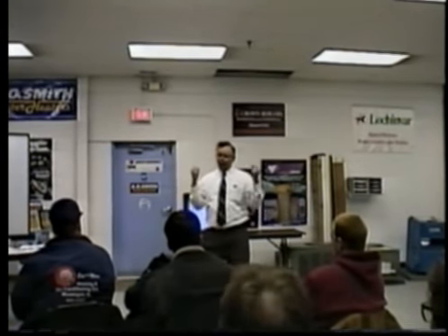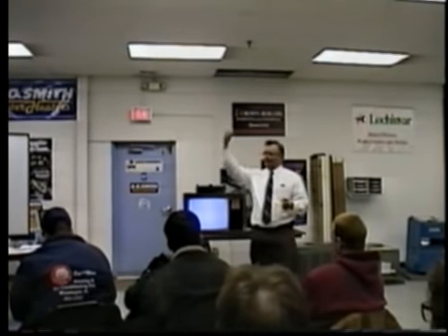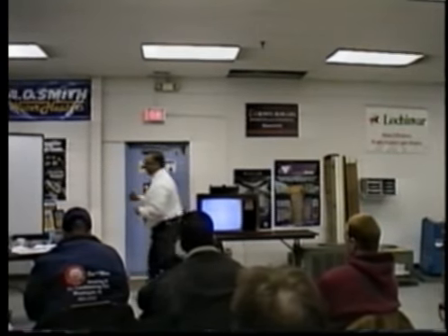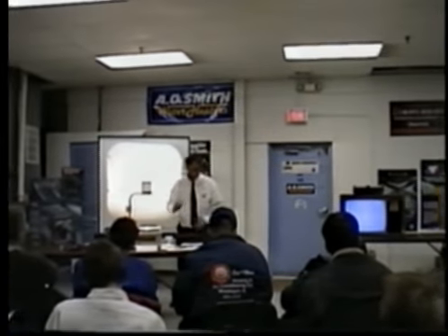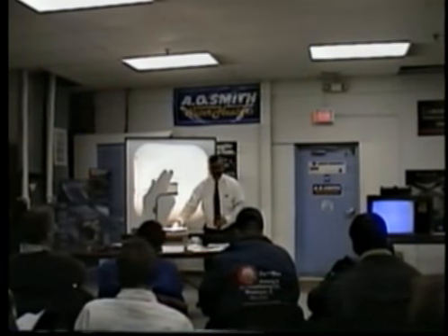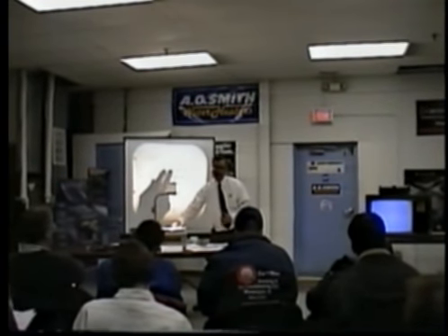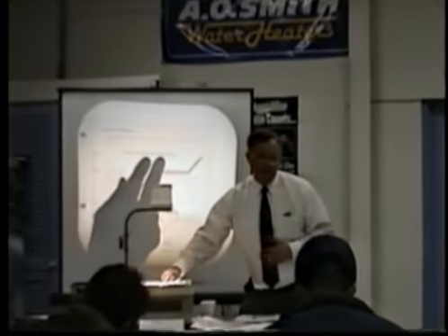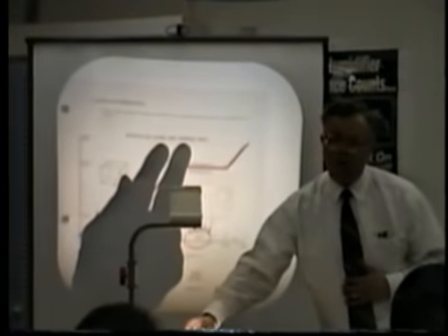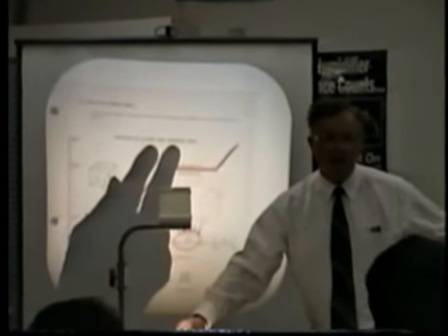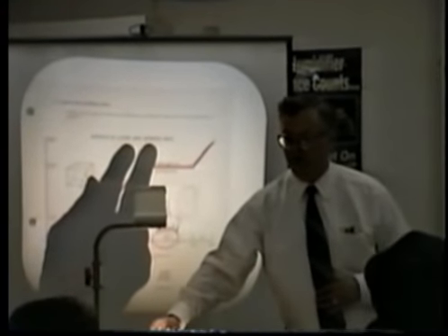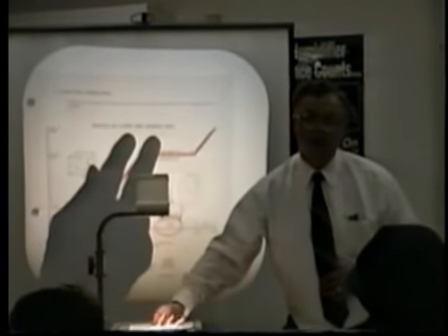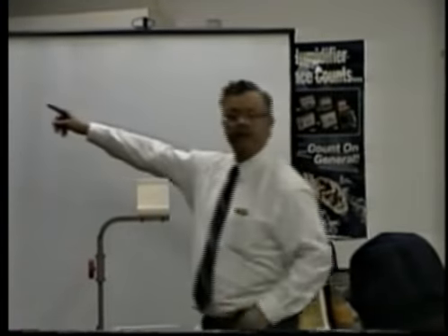So you have to size an air conditioner not only to handle the sensible heat, but the humidity, because that is the total heat load. The total heat load for air conditioning is latent and sensible heat. The air conditioner must handle both, and that's all figured into the charts. Now you understand why an air conditioner might not work on a hot day, and it's pouring water down like crazy, because it ain't big enough. Okay? You must understand this in order to understand this.